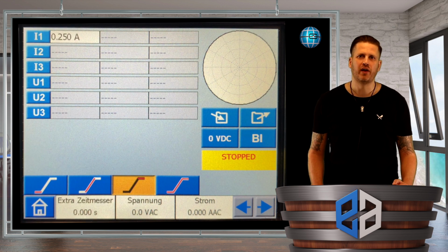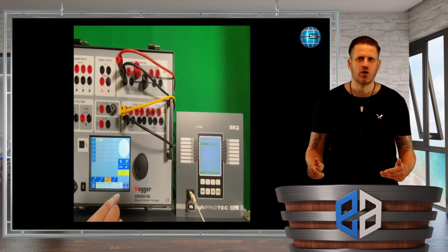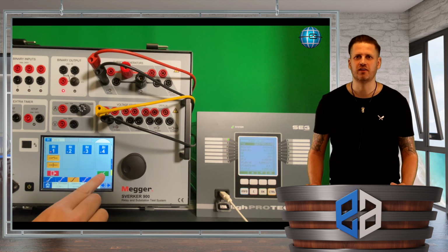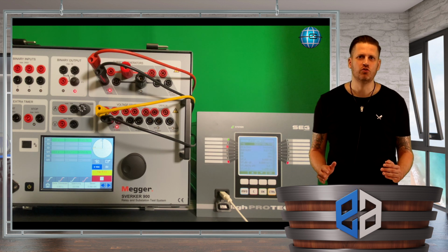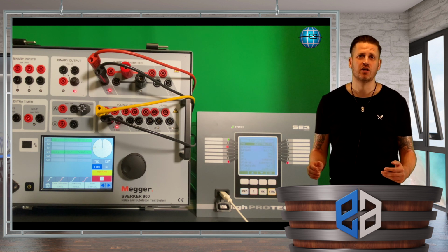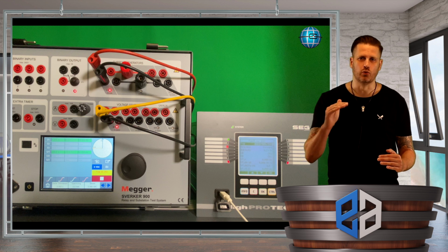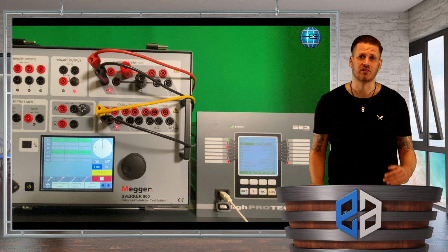To make sure that the SVERKER does not lose control when the test starts, we have to change the trigger from normally open to normally closed. The result is a release value of 245 milliamps or a release ratio of 0.98. As a reminder, the release ratio is calculated from the ratio of the release value to the pickup value, and it is dimensionless.